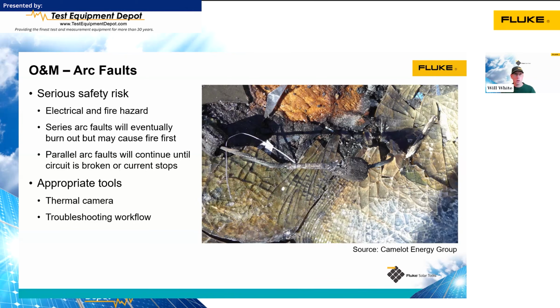Here in this picture, this was a module interconnection, like an MC4 type connector. You can see that the male side here was not inserted all the way into the female side of that connector. So there was a high resistance connection there, and that burnt out the connector and also ended up causing a fire on the roof of this building. So obviously we want to avoid them. So thermal cameras and using a troubleshooting workflow are really the only ways to find arc faults at this point.